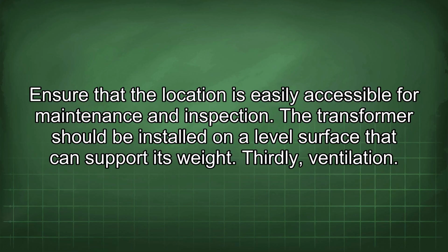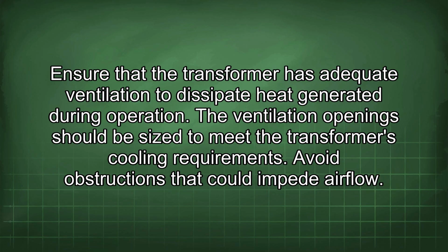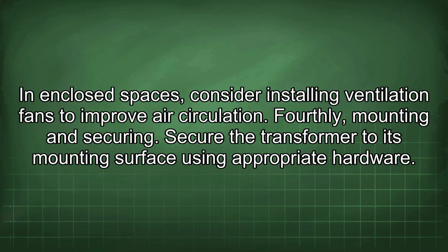Thirdly, ventilation. Ensure that the transformer has adequate ventilation to dissipate heat generated during operation. The ventilation opening should be sized to meet the transformer's cooling requirements. Avoid obstructions that could impede airflow. In enclosed spaces, consider installing ventilation fans to improve air circulation.